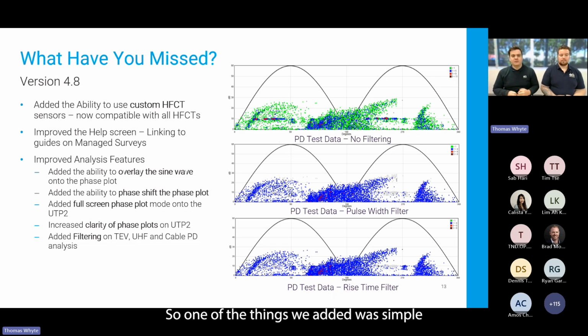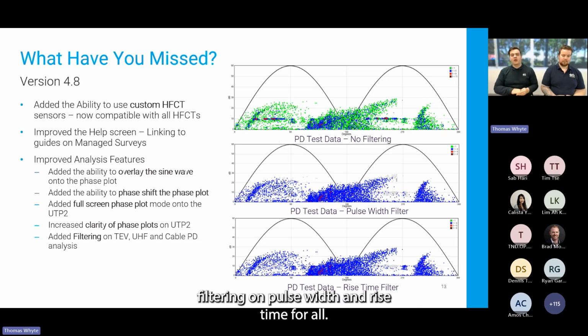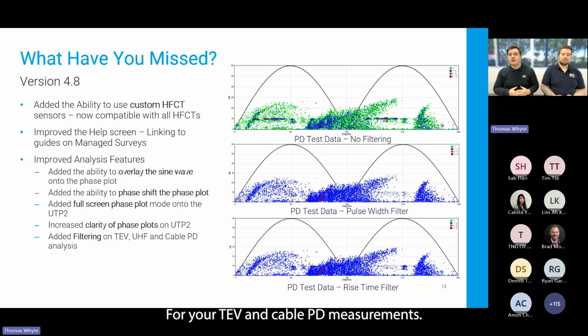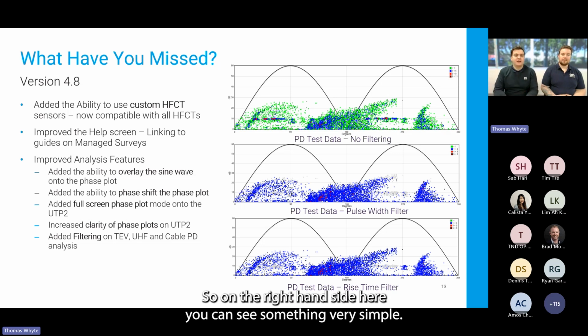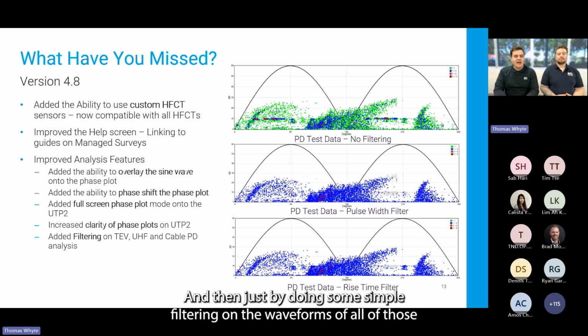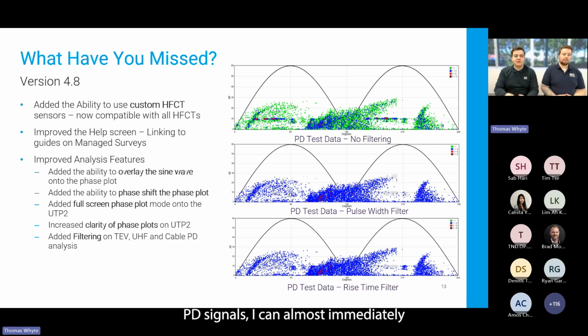One of the things we added was simple filtering on pulse width and rise time for all your TEV and cable PD measurements. On the right hand side here, you can see something very simple: a PD phase plot with multiple sources of PD with a contact noise source intermingled into it. Just by doing some simple filtering on the waveforms of all of those PD signals, I can almost immediately start to filter out that contact type noise and leave just the PD signals behind.